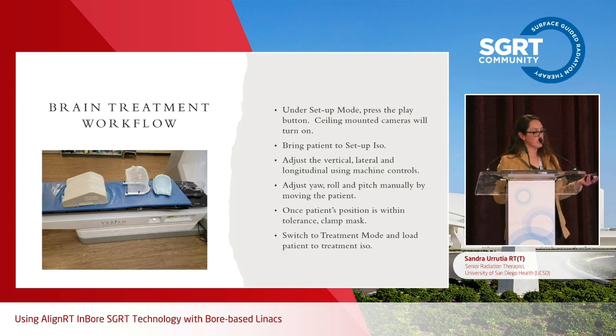And again, under the setup mode, we're going to press the play button. The ceiling-mounted cameras will turn on. We'll bring the patient to setup ISO. We again adjust the vertical, lateral, and longitudinal using the machine controls. And we adjust the yaw, the roll, and the pitch manually by moving the patient. Once the patient is within tolerance, we switch to treatment mode and load the patient for treatment.